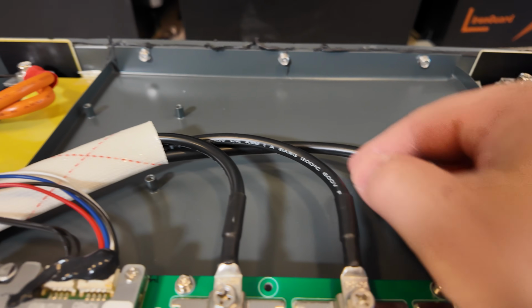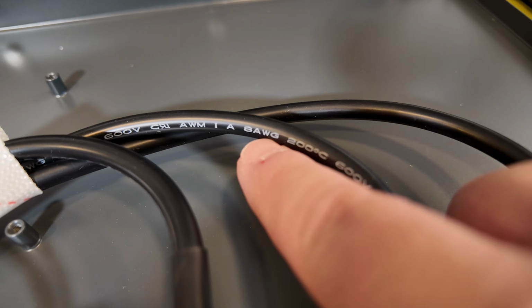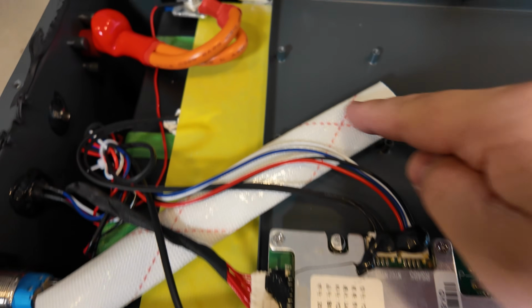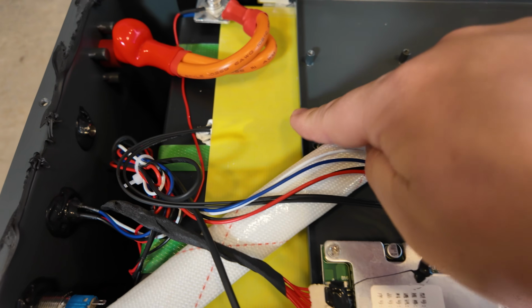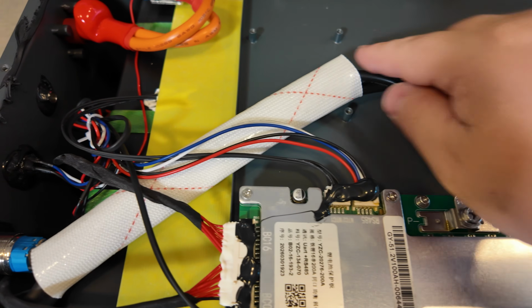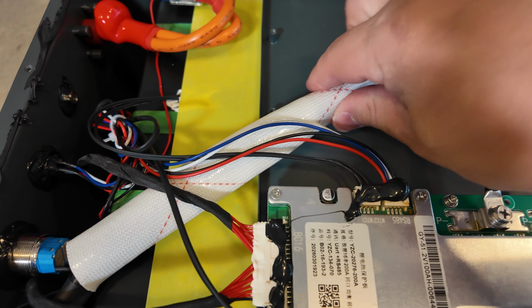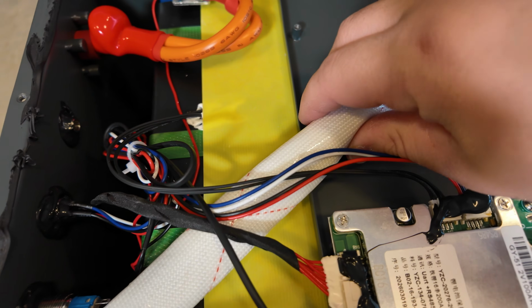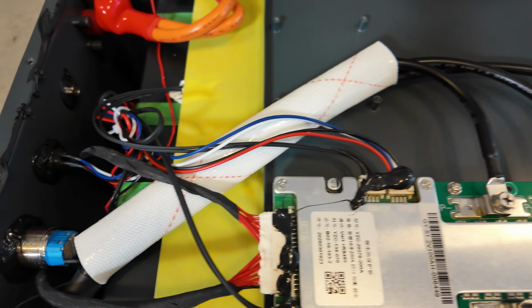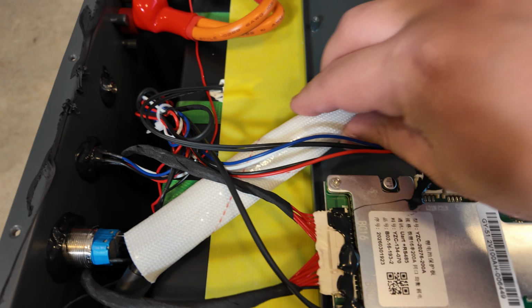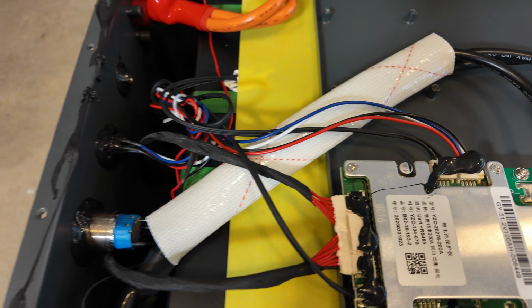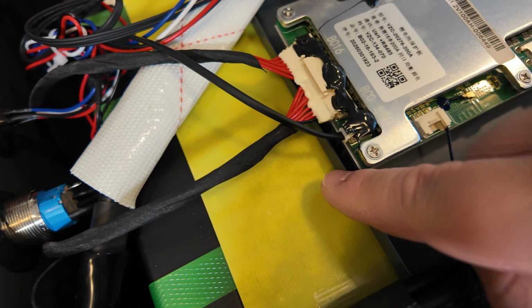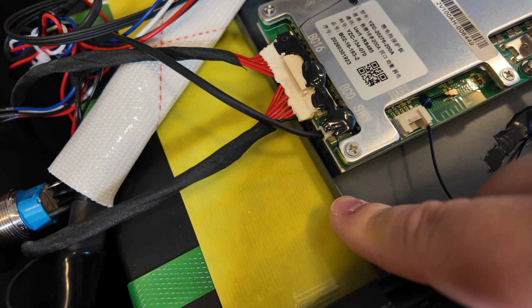On the negative side, we've got three 8-gauge conductors. I love seeing this, where the cables go over this sharp piece of metal—they've wrapped the cables in a very strong protective covering, which is good because in a high vibration environment, like a golf cart or an RV, you could get rub-throughs if it wasn't properly protected. These cables are completely suspended off the edge of the metal here.